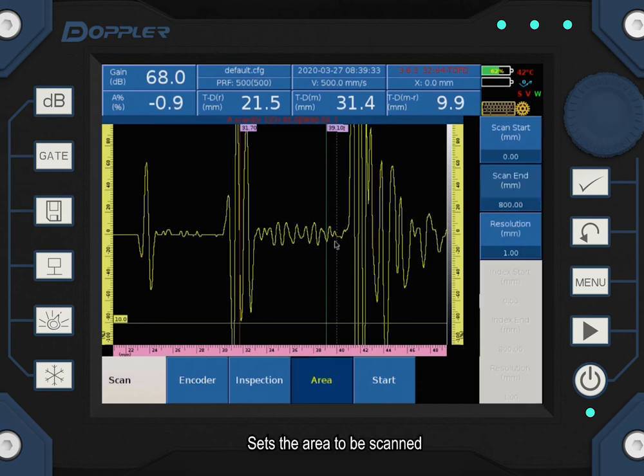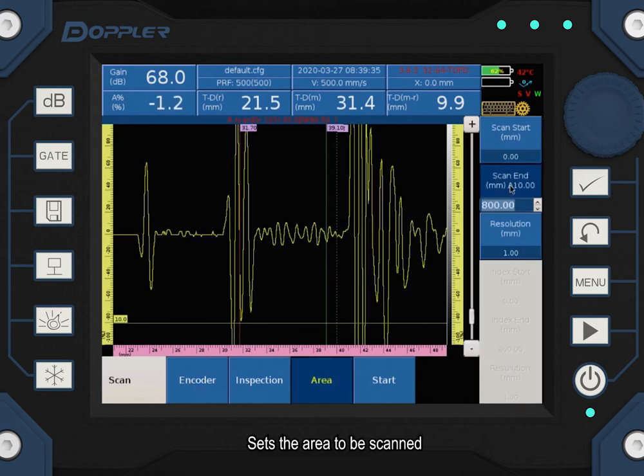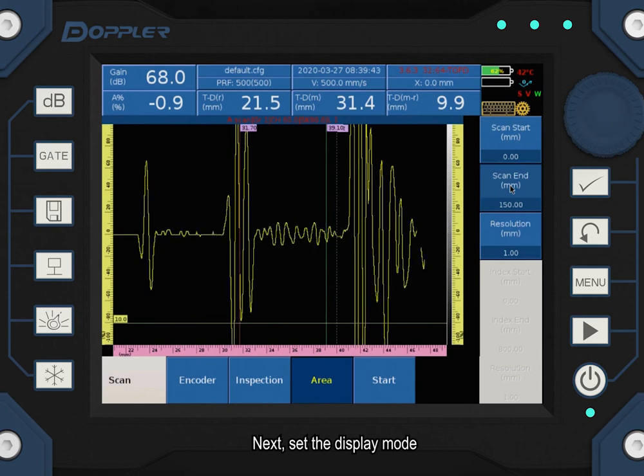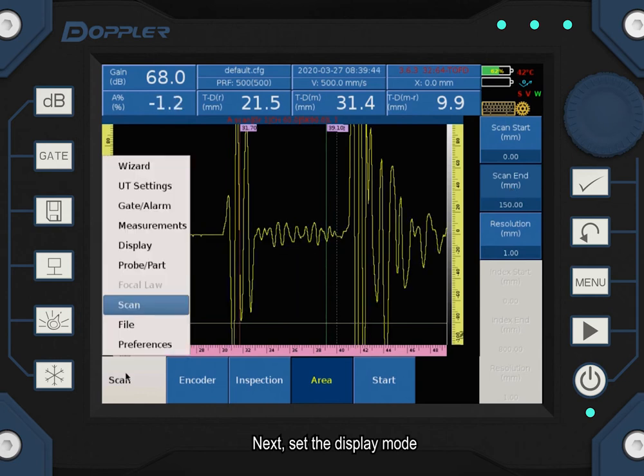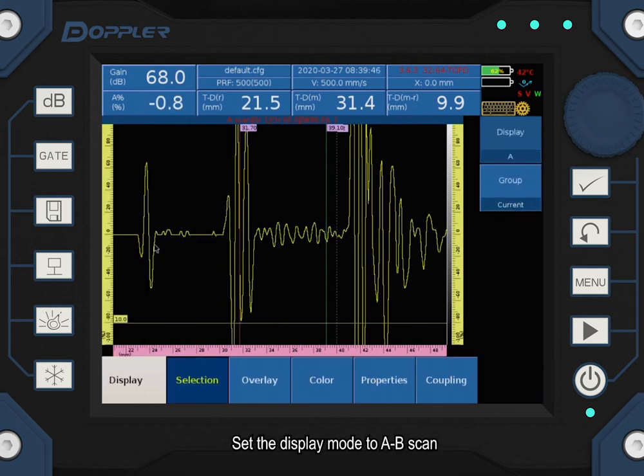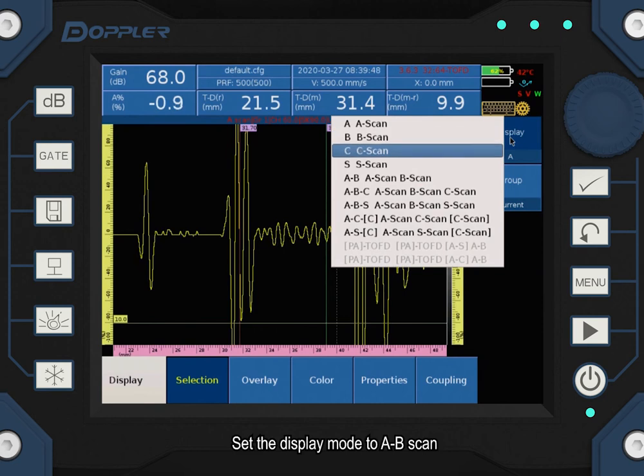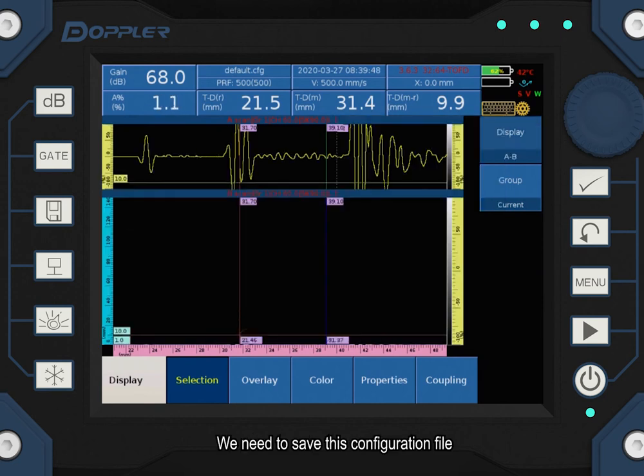Set the area to be scanned. Next, set the display mode. Set the display mode to AB scan. We need to save this configuration file.